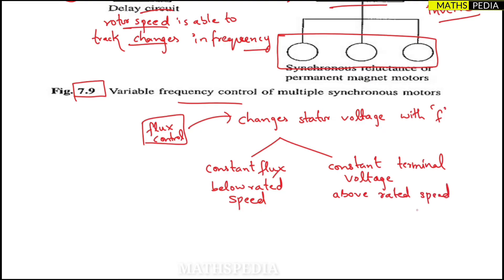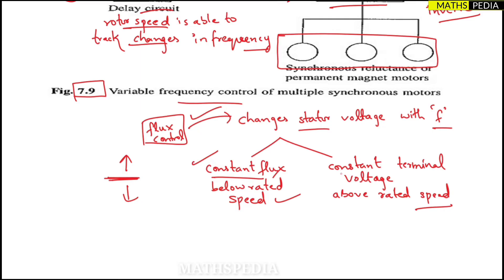The flux control block changes the stator voltage with frequency to maintain constant flux below rated speed, and constant terminal voltage above rated speed. Below rated speed we maintain constant flux, and above rated speed we maintain constant terminal voltage — that is why we are using the flux control block.